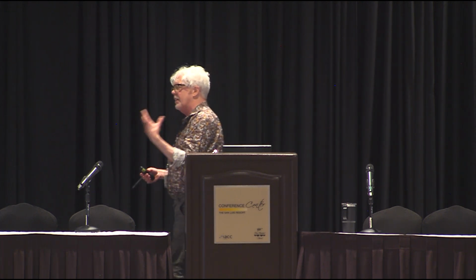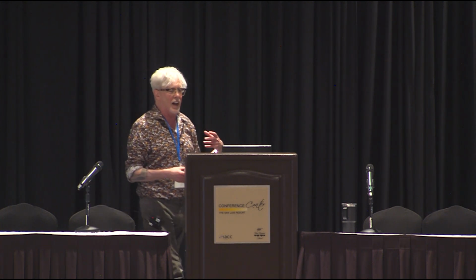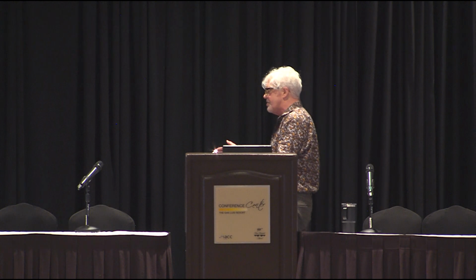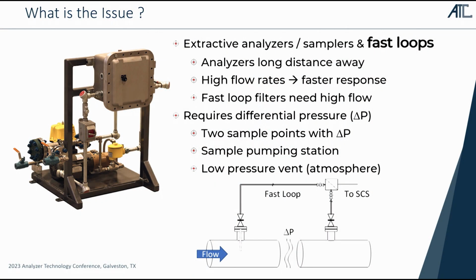The issue we're going to try to address is the fact that most extractive analyzers, most grab sampling stations, we'd like to have a fast loop there if we could. When we're looking at analytical measurements, we'd often like to get the sample there as quickly as possible, especially if the analyzer or grab sampling panel is a distance away from where we're going to do the measurement. We'd like to get high velocity flow rates over there. So let me just see if my pen's working here. No, it's not. Okay.